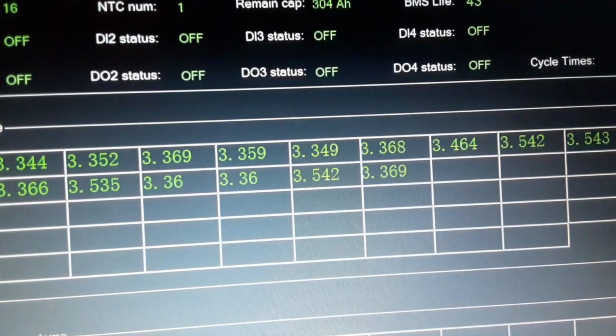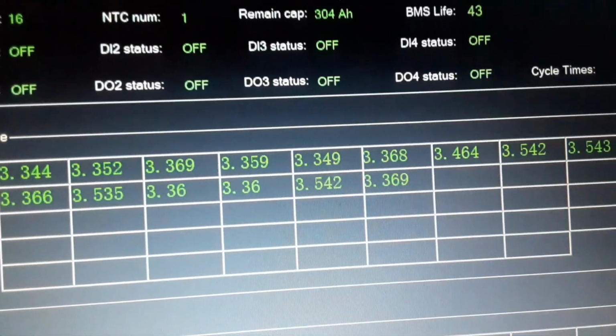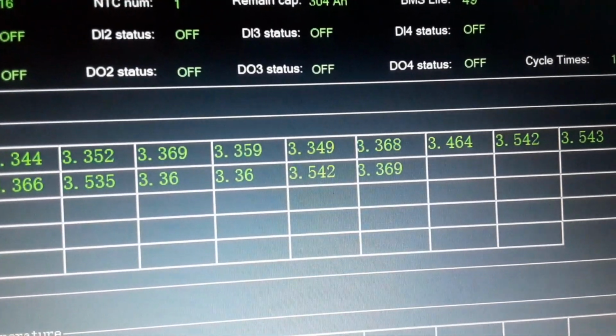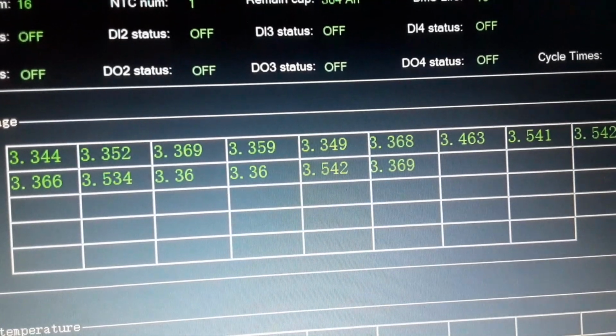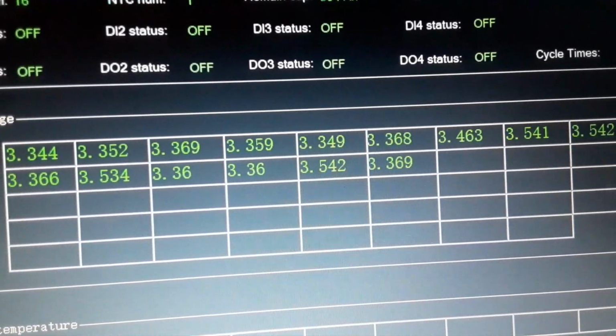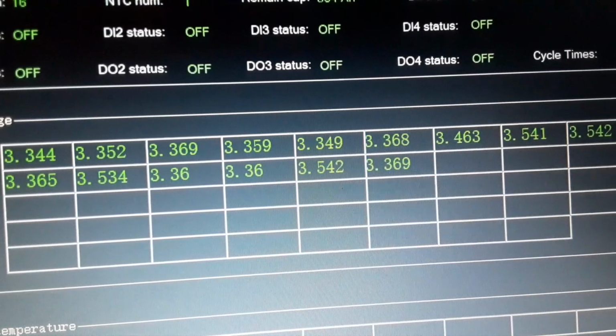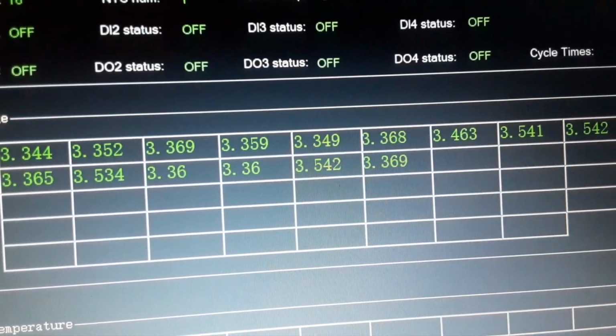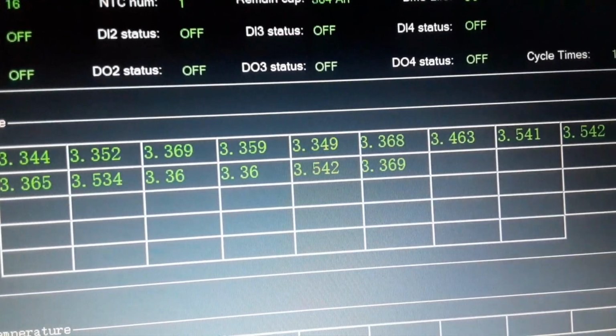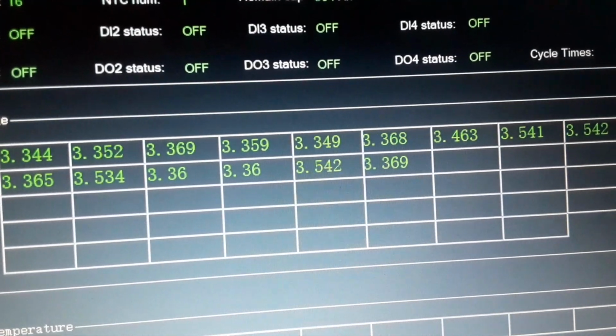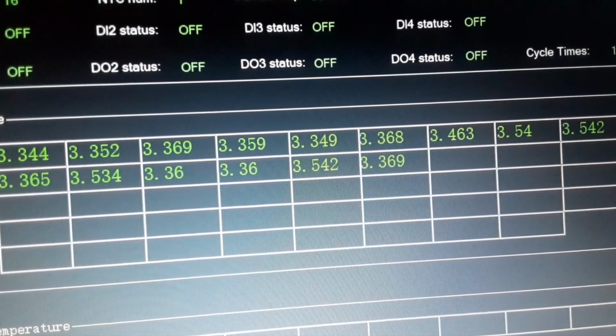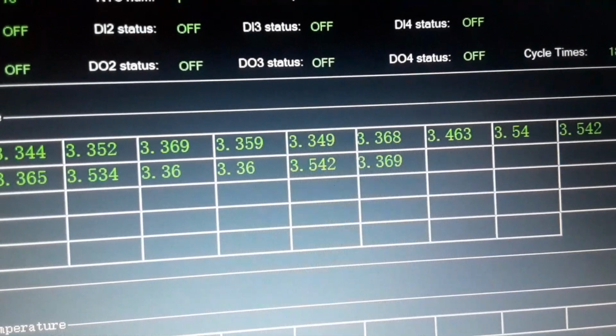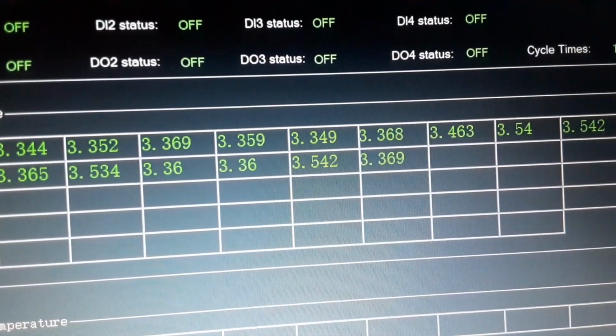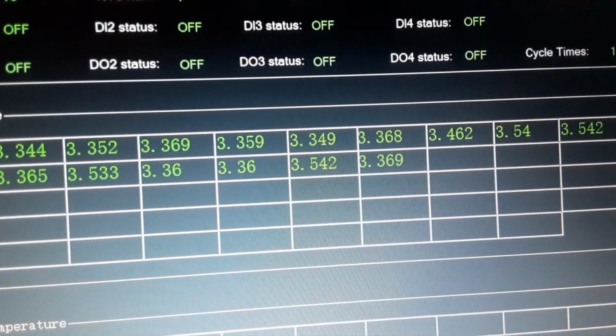This only started happening after I put my hot water heater on the 240 volt side of my 3 kilowatt inverters. When that comes on, it's spiking up to 4,000 watts, maybe 5,000-6,000 with the surge, and that was causing it to shut down. It got worse as time went on, I think because these cells got further and further out of balance.